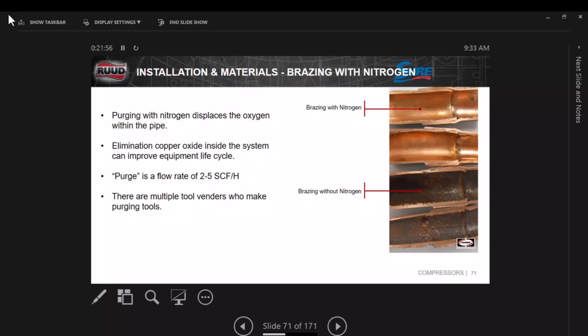And whenever we put oxygen in acetylene, or air in acetylene, to this, without nitrogen, this is what we get. Even if it was new copper, this is what we get. Perfectly clean, pretty much, and then perfectly dirty. And both these were new line sets. So how much of this black stuff is going to be there if that was a reused line set? Because all that oil that flows through there is a solvent. It's cleaning that line set up. And eventually, the inside of that line set is going to look like that.